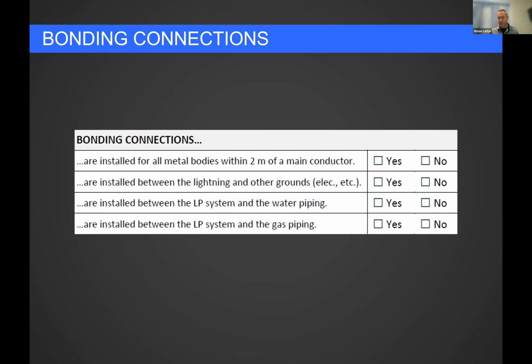Although for a low structure with down conductors close by, the bonding distance could be as low as 300, 450 millimeters. So anything over that, you don't need to bother with. Practically 2 meters is a significant jump for a lightning bolt current on a main conductor. So if you bond everything within 2 meters, you're usually fairly good. That gets you all your major bodies of inductance within the bonding distance. If you just bond them, call it a day, you don't have to worry too much about that. Have we bonded as required to the other grounds, the electrical? Have we bonded the water piping? Have we bonded the gas piping? These are the things to look for.